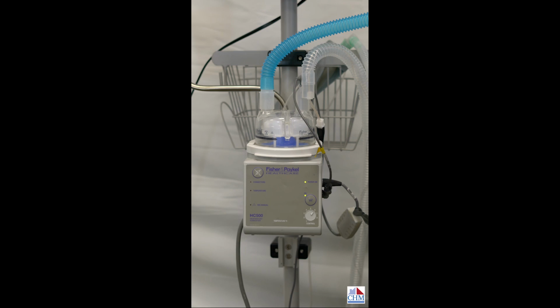So when diagnosing the problem, typically we've got a connector alarm right here. And the connector alarm can be one of usually three things. Number one, the heated wire adapter button. If we've got the heated wire on like we should with the power light, everything's working good. Sometimes this gets turned off inadvertently and we get an alarm. You can see on the left that gives us a connector alarm. So that's a real easy thing to correct.